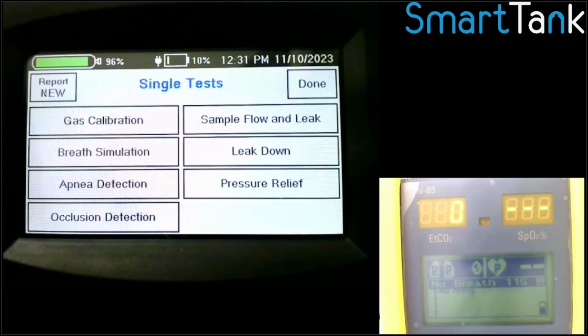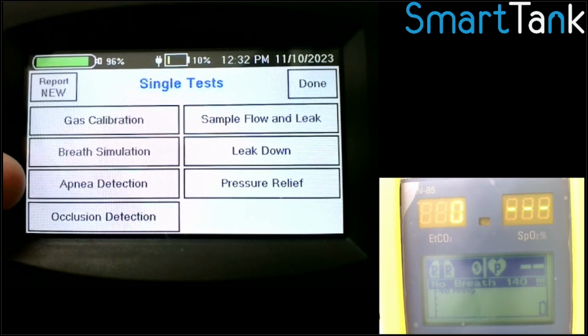Also point out that you can do leak down tests with the SmartTank. So like the PM, say, the SmartTank will actually pressurize your device and then let it stabilize, start a timer, take a reading, start a timer, and then take the final reading at the end of that time, and then tell you the drop in pressure. So it will do that automatically for you. A lot of the sequences have that built in, but the one I showed you does not. You can do other alarm things. It'll even do pressure relief.